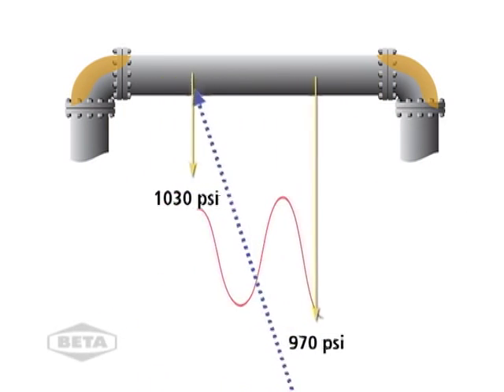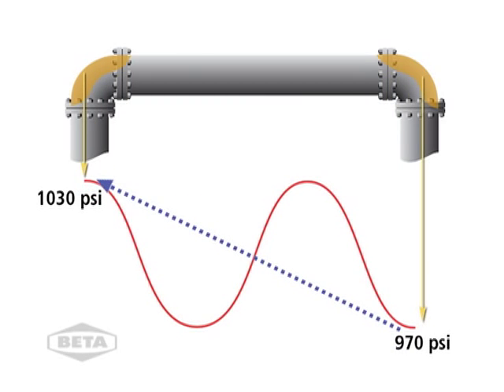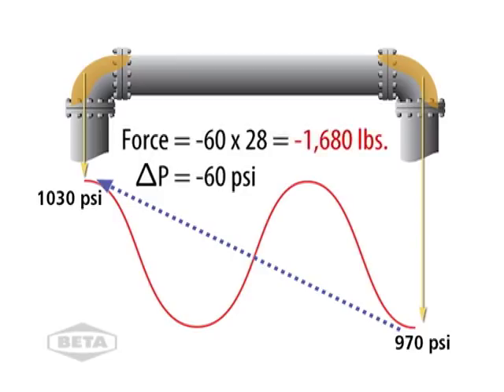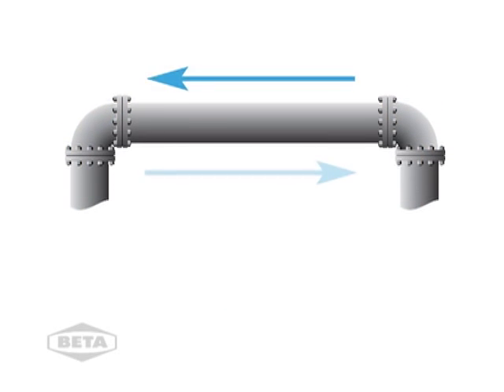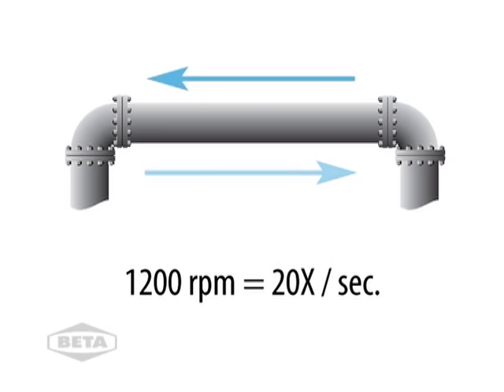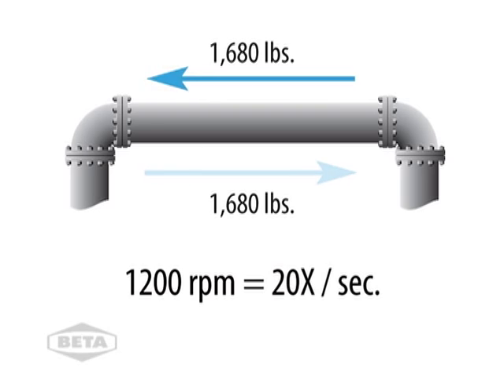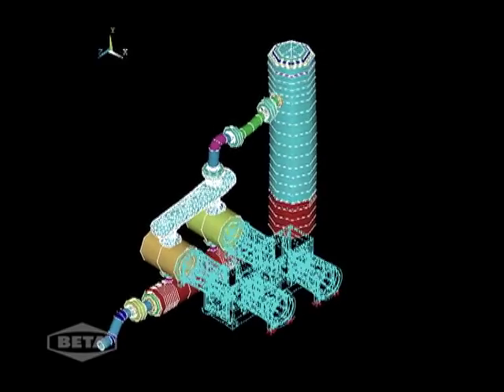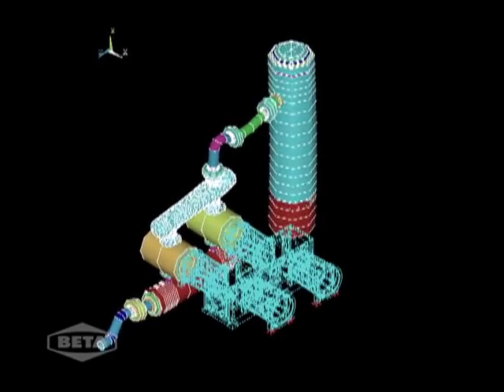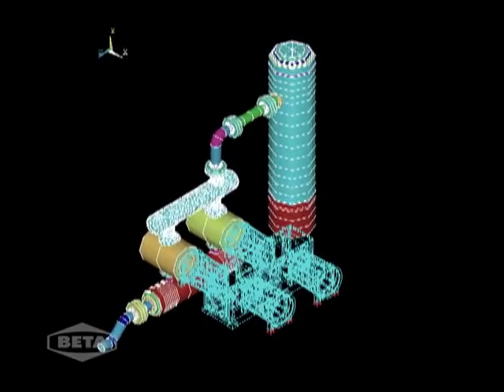As the pressure wave travels 180 degrees, the differential pressure reverses direction and is now minus 60 psi. The unbalanced force is now 1680 pounds in the reverse direction. The force oscillates back and forth at the run speed. For a 1200 RPM machine, the frequency is 20 times per second. This means the unbalanced force of over 1600 pounds is shaking back and forth at 20 times a second. This puts extreme stress on clamps, bolts, and sleepers, trying to hold the pipe in place.